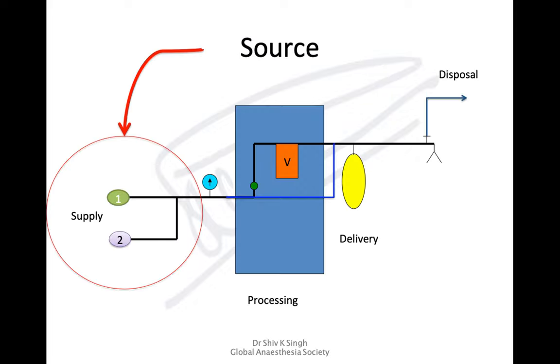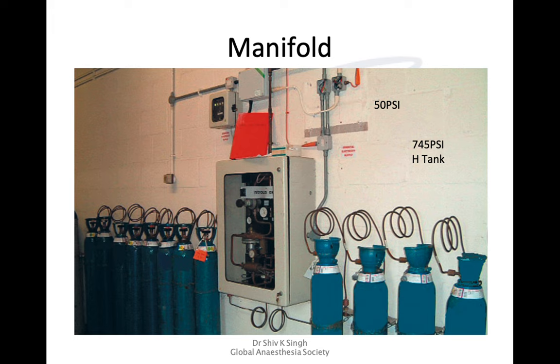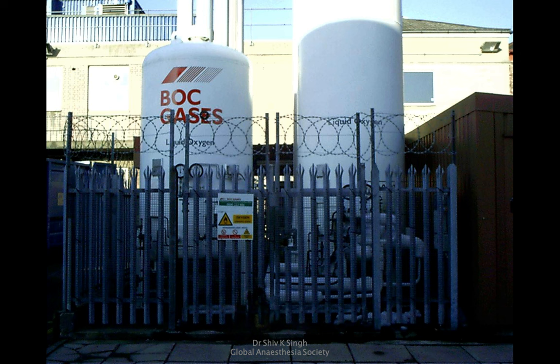The sources include cylinders and the VIE. VIEs are also known as cryogenic liquid systems (CLS) and are found outside the hospital. They operate at high oxygen levels and can also come from the manifold rooms within the hospital. The cylinders in manifold rooms are H-type cylinders at 745 psi — very high pressure — and pressure regulators reduce this to around 50–60 psi in the pipeline.